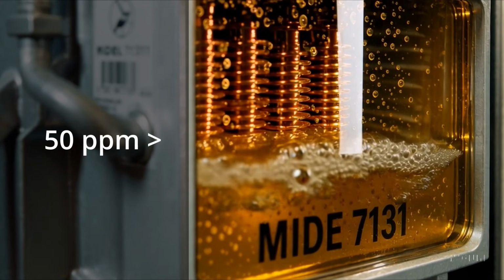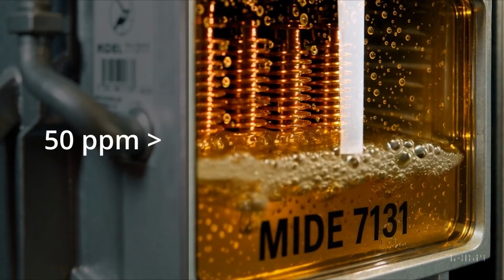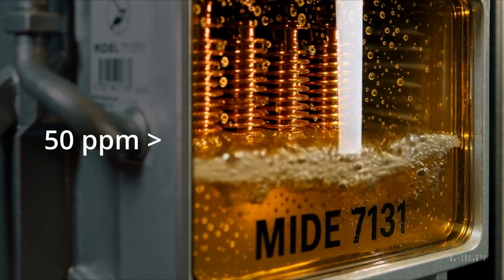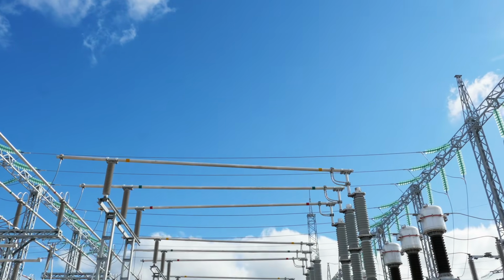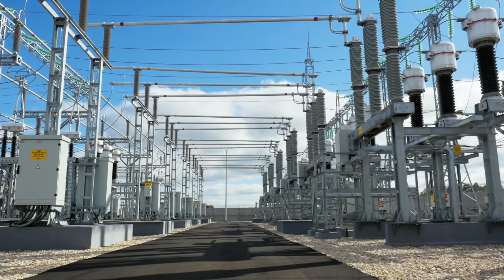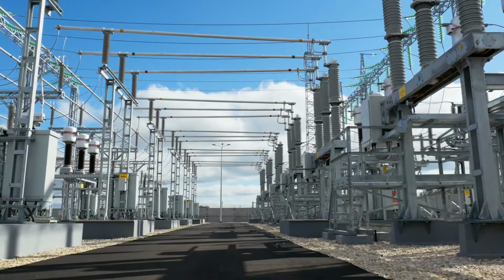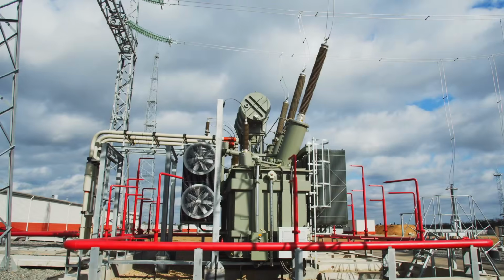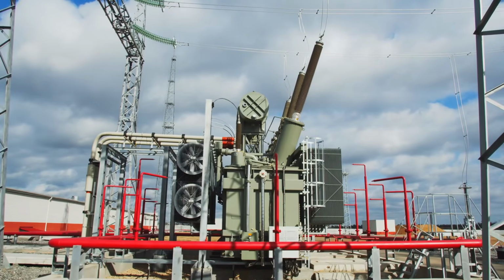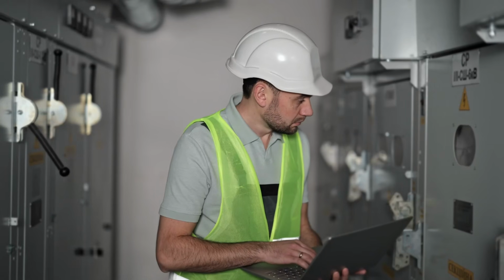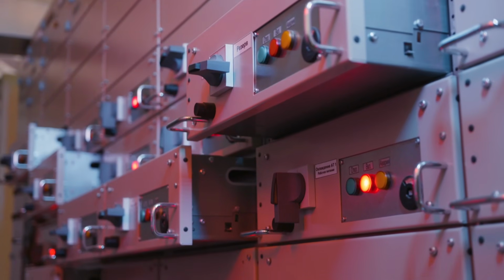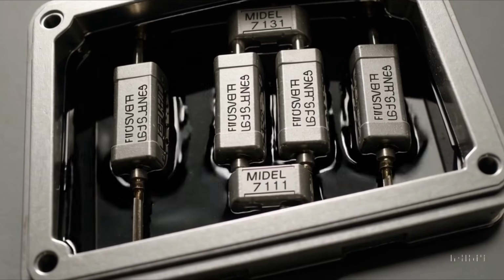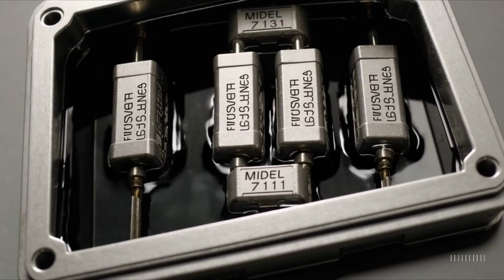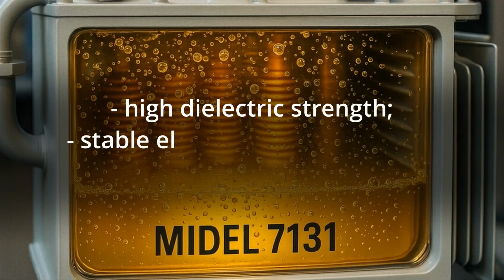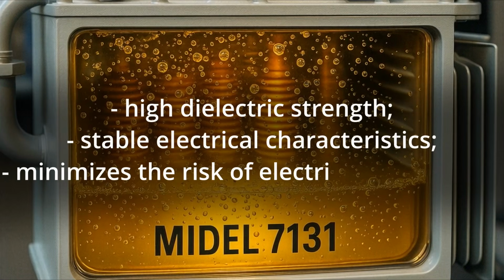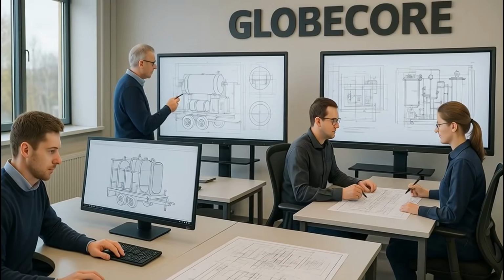However, even with this feature, in order to ensure maximum electrical safety and stability of parameters, the fluid requires dehydration before bringing into use, especially when it comes to power supply and distribution transformers, voltage regulators, cooling systems for power electronics, thyristors. Dehydrated and degassed MIDEL ensures a high dielectric strength, stable electrical characteristics and minimizes the risk of electrical breakdown. GlobeCore professionals have developed 3 technological solutions adapted to different moisture levels of MIDEL 7131.